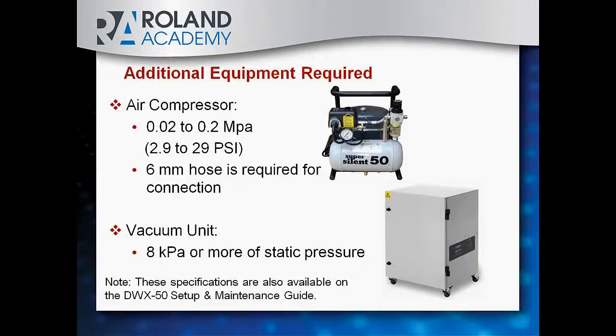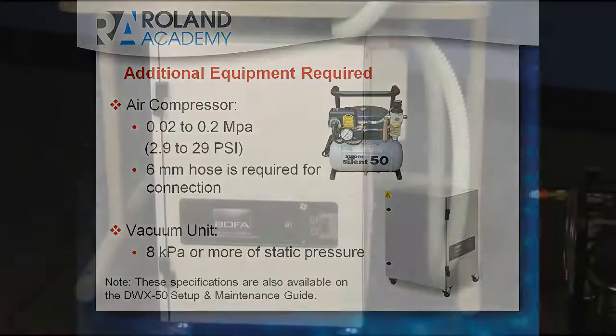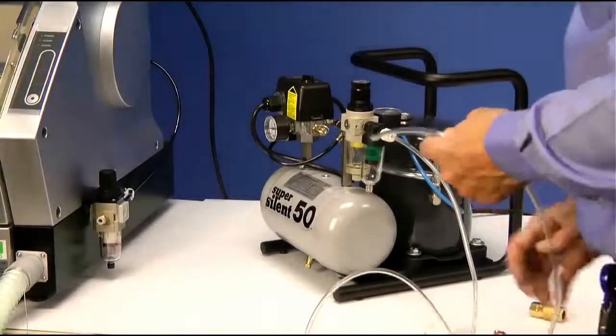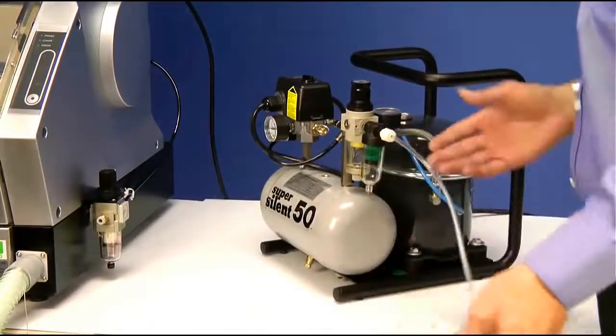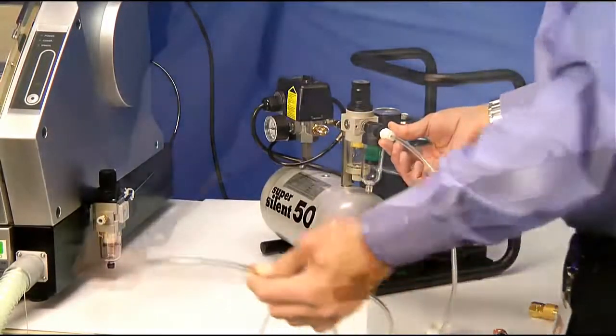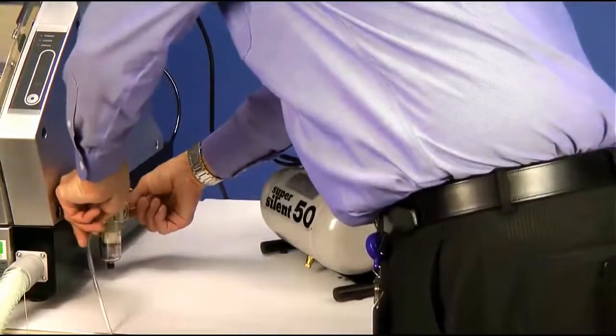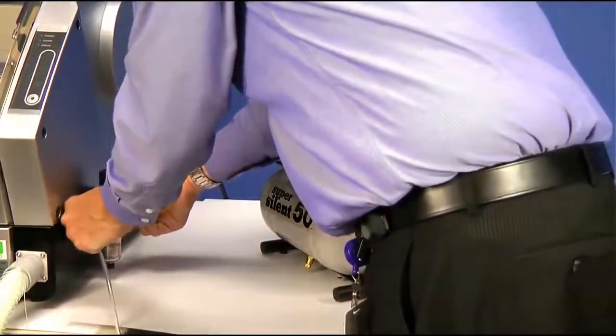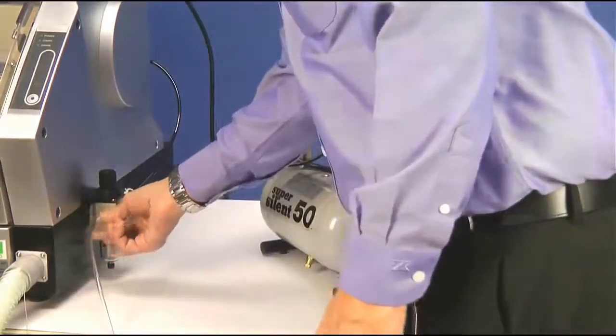Next, you will need a vacuum system and an air compression system that meet the specifications listed on the spec sheet in your documentation for the machine. Once you have your air compression system, take your polyurethane tubing, it needs to be 6 millimeters, press it in flush into the regulator's quick connect valve, making sure there is no air leaks.